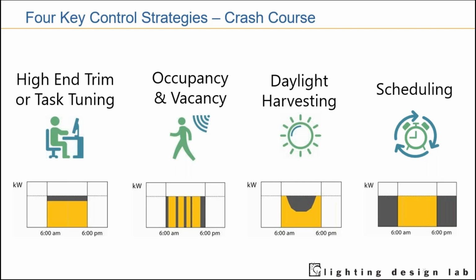When we talk about daylight harvesting, for a specific task plane, be it a desk, a whiteboard in an office, or a classroom, whatever the case may be, the IES recommends a specific amount of foot candles for these tasks. Let's say there are windows, skylights, or some kind of fenestration in your space. If your natural daylight gets you 80% of the way to your recommended or required foot candles, and you only need 20% of electric light to take you all the way there, there are savings to be made and a lot more comfort and productivity for your tenants.